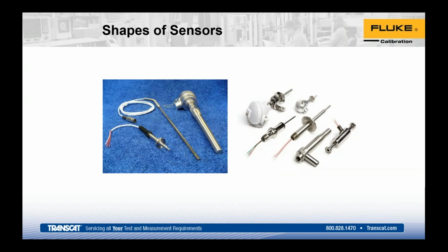A lot of times with some of these sensors, the calibration of the actual sensing element is predetermined before it's built into the housing of the sensor, which poses the problem I spoke to after the fact, because you're now stuck with this housing. And you're limited to a dry well or a bath, and maybe it's outside the temperatures you could achieve, and you need to get a big furnace involved. But now I need 12 inches of immersion, and I've only got 3 inches of a probe. So again, there are challenges based on the shapes of sensors.